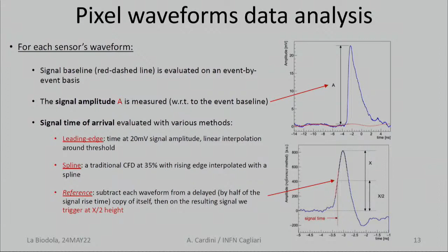We have a leading edge algorithm. So we have a linear interpolation of the rising edge, and then we trigger usually around 20 millivolts, slightly above the noise. We have what we call the spline, and this will be shown in the previous plots. It's a traditional constant fraction discriminator implemented in software at 35% of the total amplitude. And then we have, let's say, a 100% constant fraction: we subtract from each waveform a delayed version of itself, delayed by half of the signal rise time. Then we trigger at 50%. So these are the methods we use for timestamping.